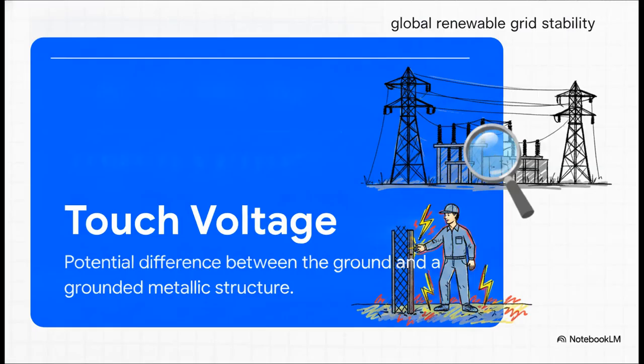Before we crunch any numbers, we need to clearly define the two main ways a human can be lethally shocked during a substation fault. First up is touch voltage. This is the voltage difference between the ground you're standing on and a grounded metallic structure you happen to be touching with your hand. The second is step voltage. This is the voltage difference between your two feet as they're spread apart on the ground while a fault current is flowing through the earth right beneath you. Both of these scenarios can absolutely be deadly if the engineering isn't flawless.